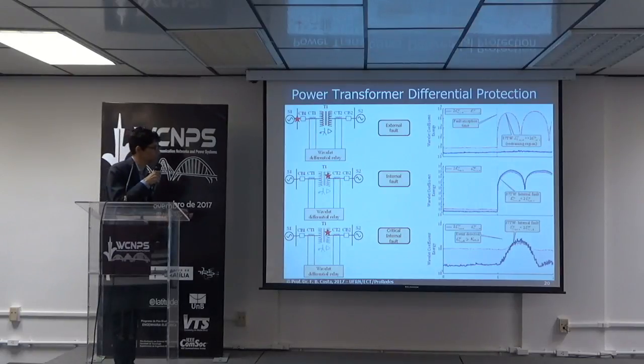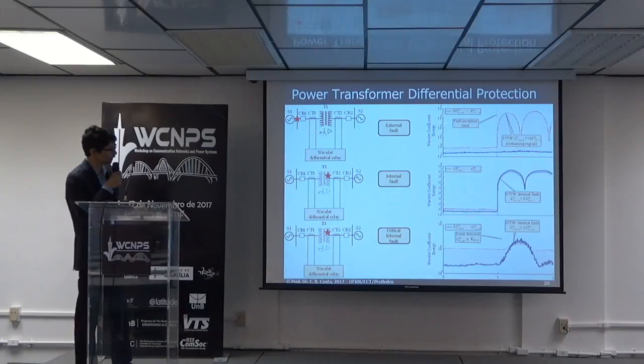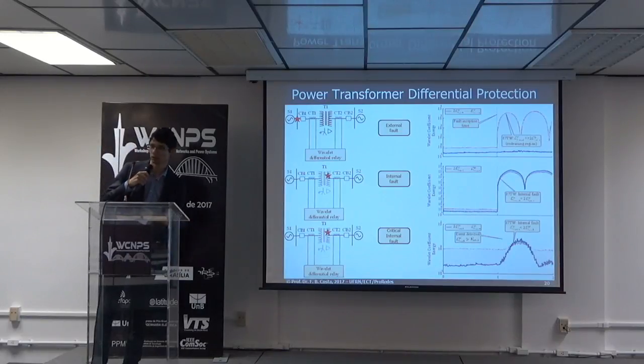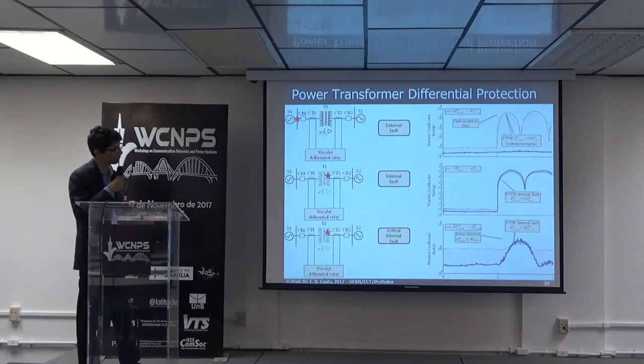Here we have some examples, for instance, an external fault here and an internal fault in the power transformer. By using the wavelet information, the restraint energy obtained with the Wavelet Transform presents this feature. However, in an internal fault, the blue line, which is the operational energy, could increase so fast. Here, the external and internal faults could be differentiated and detected in microseconds. Here is another example. This is a critical internal fault in a power transformer that the conventional one could not detect. However, the Wavelet Transform, which is very sensitive to transients, could detect this kind of fault.